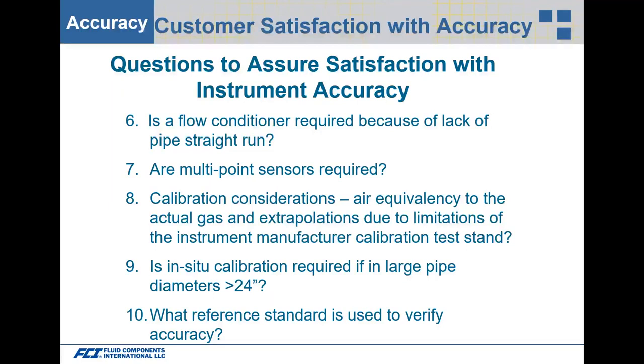Is a flow conditioner required due to lack of pipe straight run? If you have less than 10 to 15 pipe diameters, you'll want to look at a flow conditioner to condition the flow profile. Are multipoint sensors required? Sometimes you can use many flow elements going back to one transmitter, averaged for flow output. Calibration considerations include air equivalency to the actual gas and extrapolations due to test stand limitations — some labs can't cover your full flow range and must extrapolate the non-linear curve, which isn't ideal.